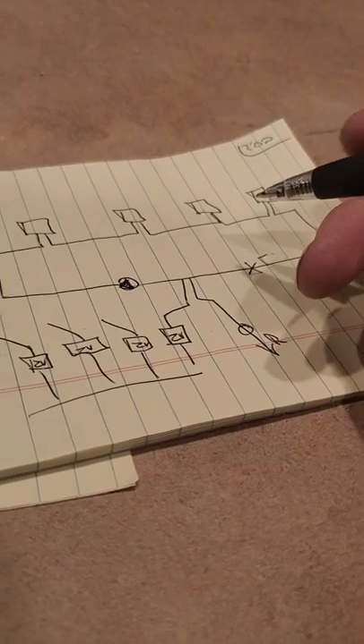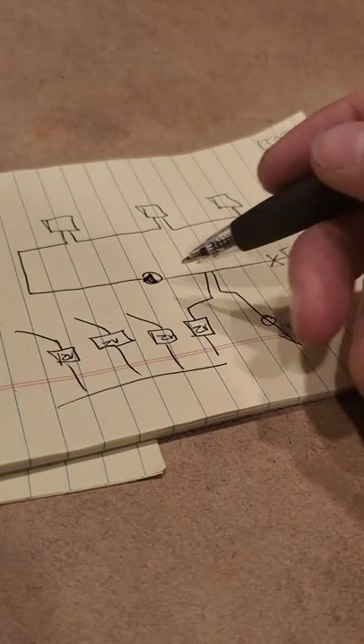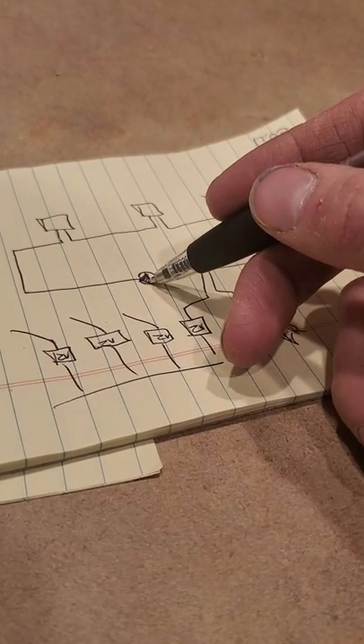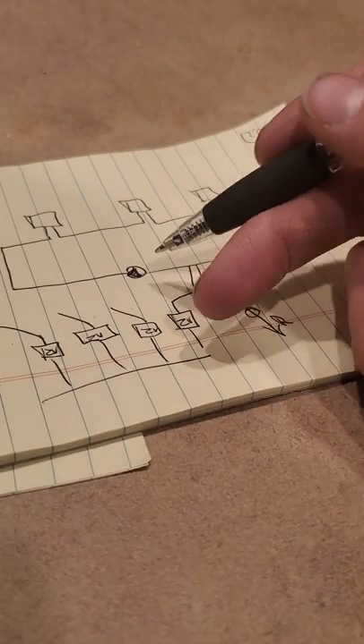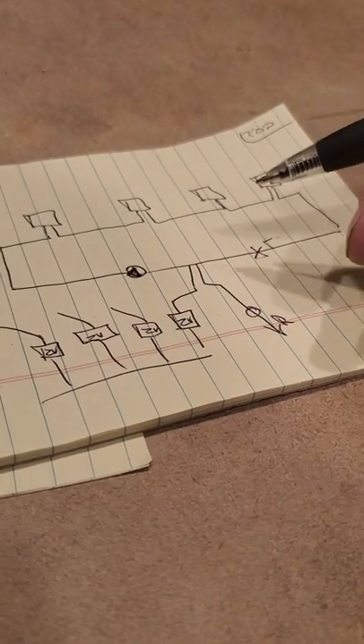So now what you guys are thinking is, okay, moving water doesn't freeze. I got it. This is going to run any single time the boiler runs. And that is true. Anytime the boiler is powered, this is going to use 0.7 of an amp. Don't cry to me about the electric usage and the pump's going to die. It'll last 15 to 20 years and if it dies sooner, it's a cost of doing business.